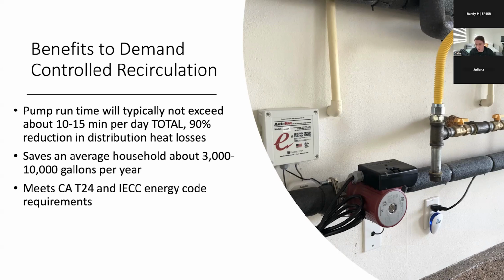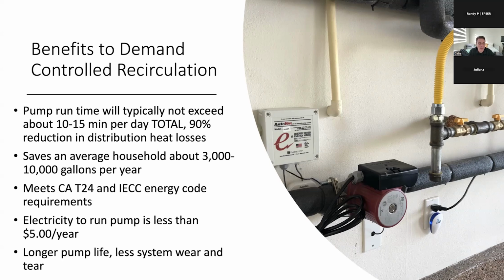And you get, obviously, the convenience of getting hot water fast. I think that's what most homeowners really want and appreciate: I just don't want to turn on my shower and then go do something else for 5 minutes, right? I just want the hot water to come out right away. So it's the convenience factor. On demand does meet IECC Energy Code requirements. And the electricity to run the pump typically costs less than $5 a year to operate the system. So it's extremely energy efficient. And you're going to get a much longer useful life out of the system.